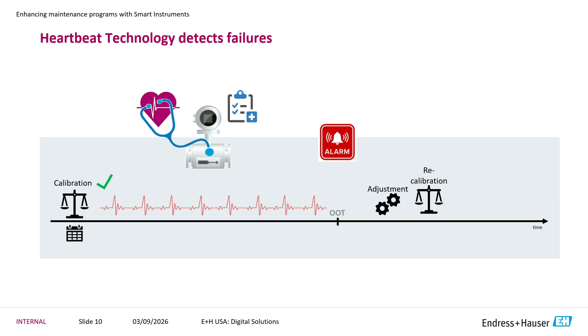As I mentioned, the heartbeat technology is almost constantly taking these pulses. When you get an alarm, it's actually going to alert you, and you might adjust your calibration earlier. So we're doing it when it's needed, not just because the timestamp says 12 months is up, now you have to calibrate.